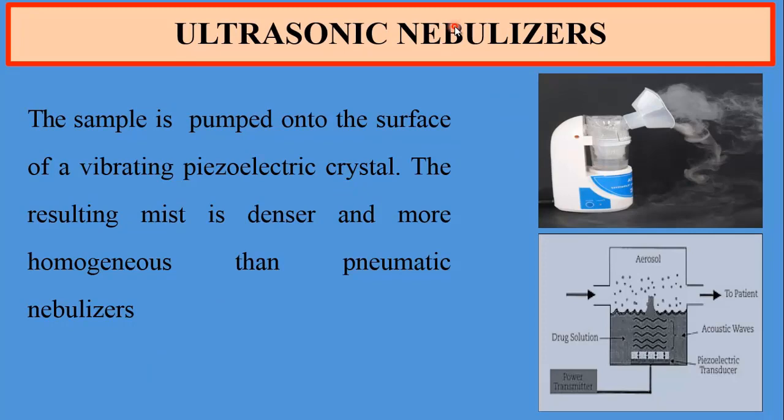Ultrasonic nebulizer. In the ultrasonic nebulizer, there is a piezoelectric transducer which converts the electrical signal into an acoustic wave. This acoustic wave will convert the sample into a small aerosol, and this will convert it into a homogeneous form. So this is better than the pneumatic nebulizer.